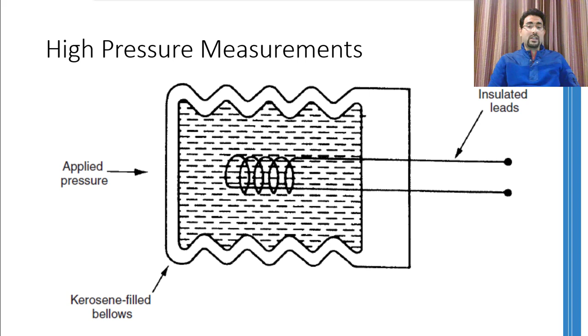So these were all the pressure sensors that I have to discuss. Now, which pressure sensor you can use in what situation depends on a number of factors. First of all, the range of pressure that you want to measure dictates the type of pressure transducer you can use. Normally, in industrial practice, any pressure between 1 to 7,000 bars is considered as mid-range pressure, anything below 1 bar or below atmospheric pressure is considered as low pressure, and anything above 7,000 bars is considered high pressure.